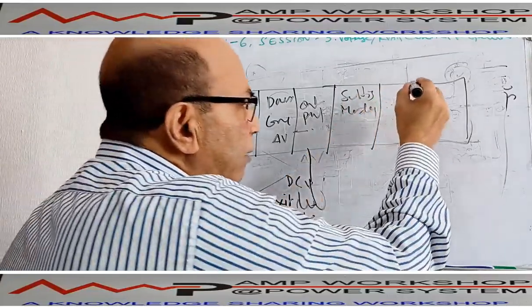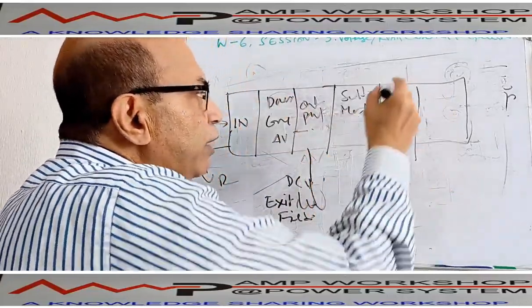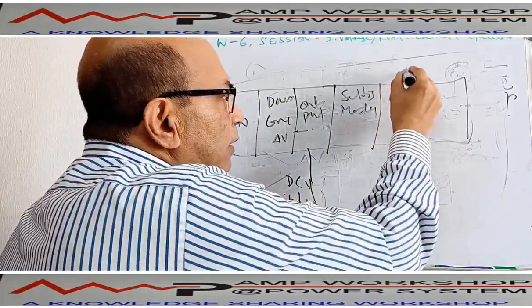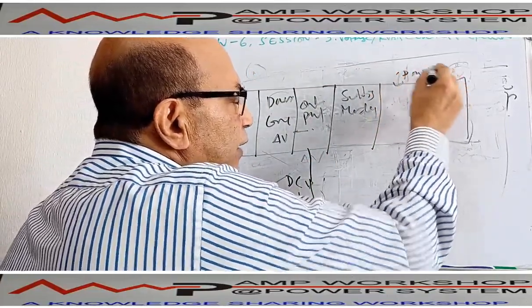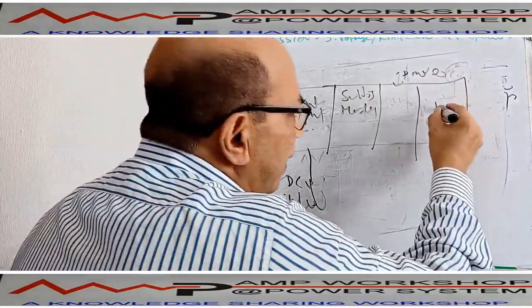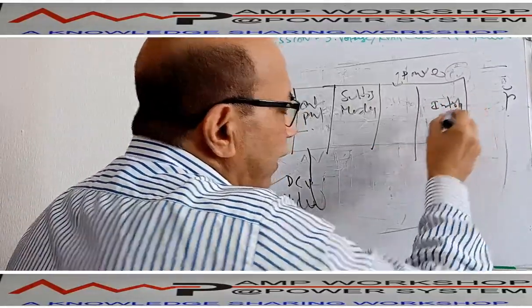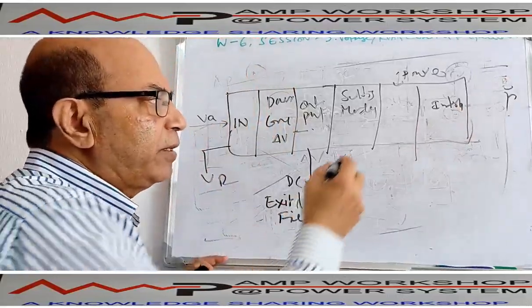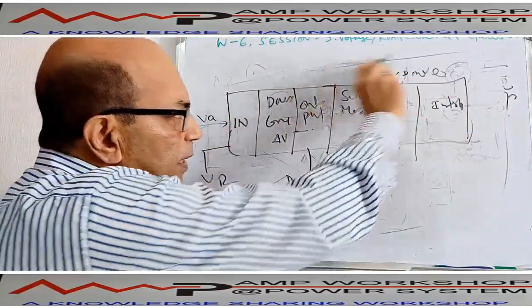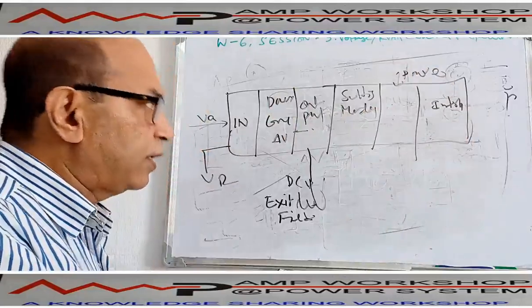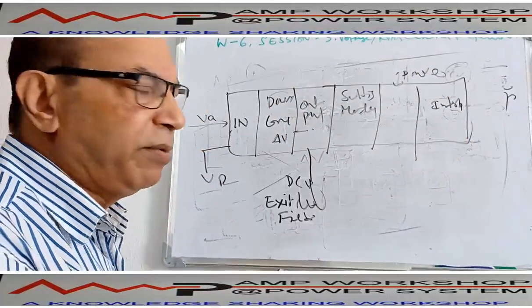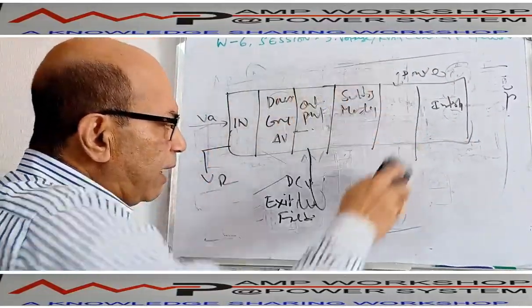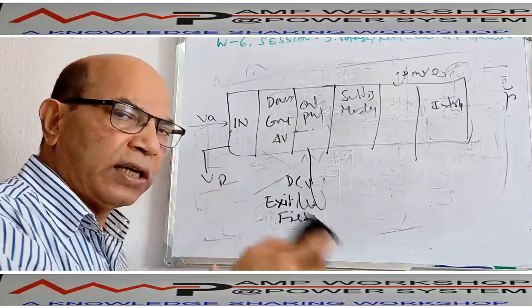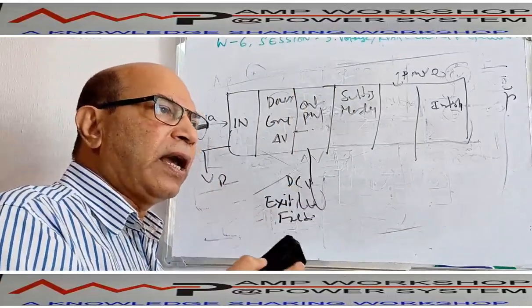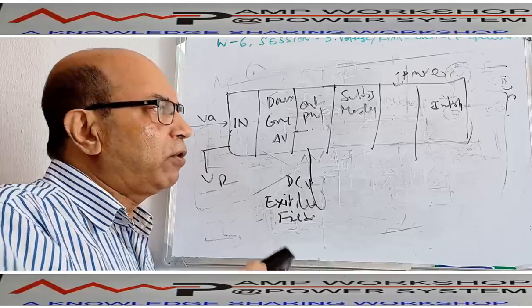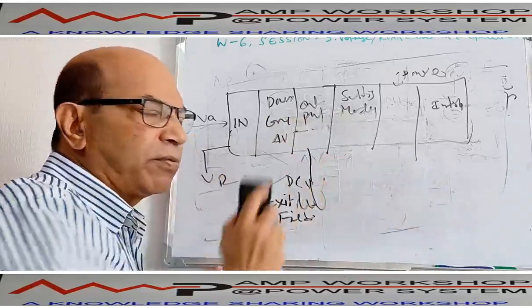Then, to operate this thing, you need power supply. So there will be a power supply module. It will need some auxiliary power supply. Then it has an interface section which can be connected with other governor or load sharing, whatever is required. So a typical control device has this type of section, five to six sections. Now when this device is operating, this is how the input signal is received and how the voltage is controlled, that we can make out from here.